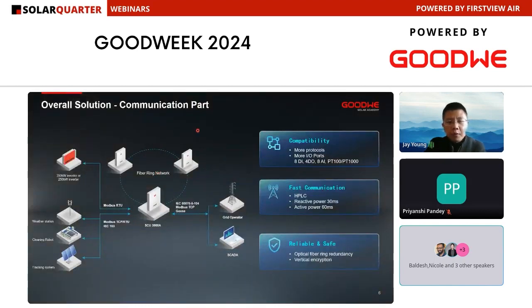So we can provide you a total solution for the utility station. Let's focus on the communication part. We have our SCU 3000A data logger. It can communicate with our inverters through Modbus RTU, and it is compatible with third-party equipment like weather station. It will collect all the data from the inverters and the third-party equipment, and send it to the SCADA system through IEC 104, Modbus TCP or GOOSE protocol. For the SCU itself, we can make a fiber network, so every SCU, every data logger, is redundant to the others. So it will make the communication more stable.